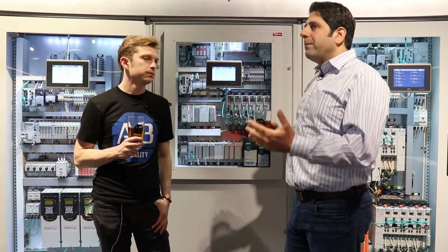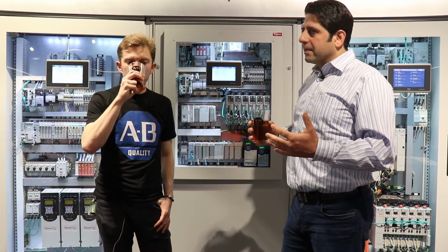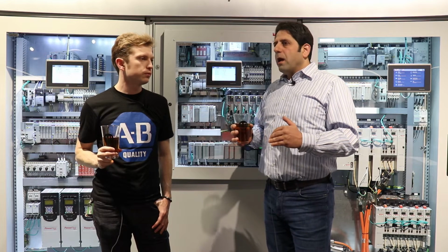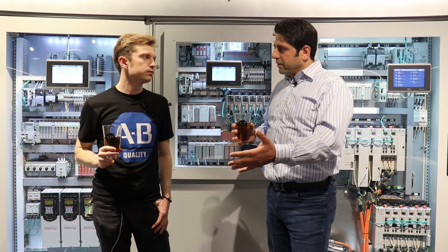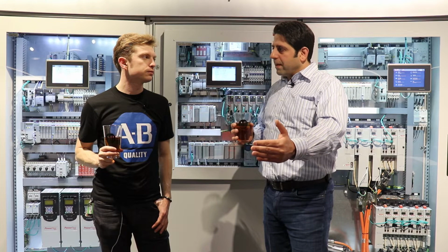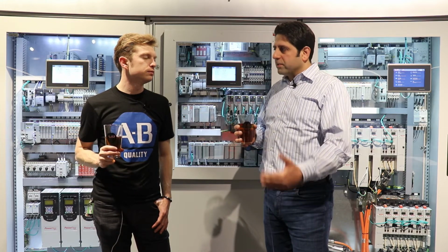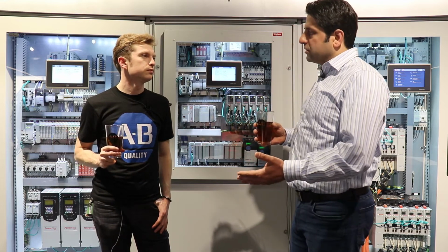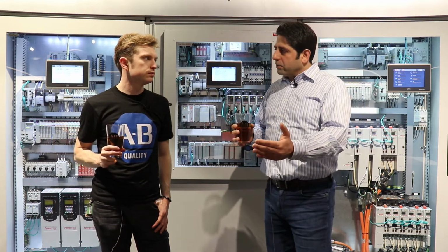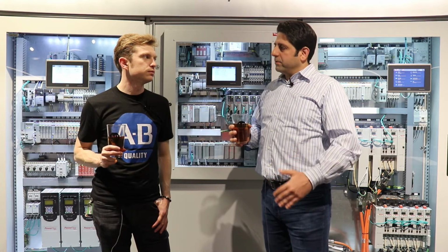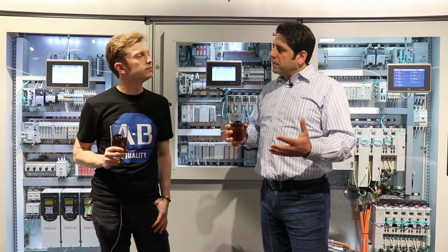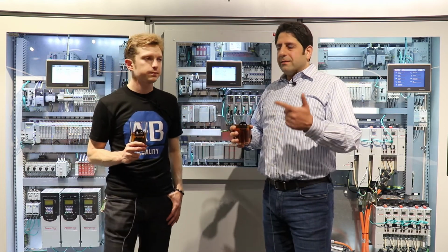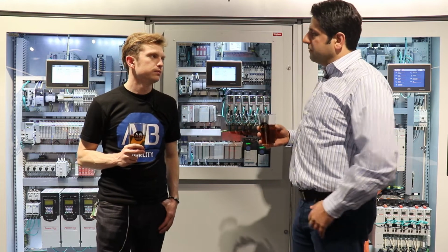controllers. What we mean by enhanced integration is that in addition to just basic device status, faulted, not faulted, out of a PowerFlex 755, for example, we're able to connect directly to that PowerFlex and read its drive parameters. The same is true for CompactLogix and ControlLogix controllers. We connect directly to that controller and we're able to read its tag values. Other data sources for TeamONE would be a FactoryTalk Alarms and Events server, as well as the action cards from a FactoryTalk Analytics for Devices appliance.